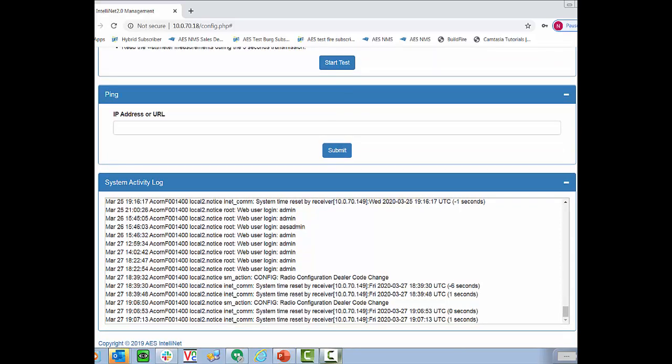Below we have ping where if you're using an IP connection you can ping the multinet receiver. And then we have system activity log. One of the main reasons I'd want you to set up individual usernames and passwords is so you can see exactly who made any changes to the subscriber. Notice here it will always say admin admin admin because this is the only user set up on this subscriber. If you had individual subscriber IDs you could see exactly who did what in your subscriber. This is very handy for service technicians. Two weeks ago the subscriber stopped working and they want to see if there were any changes that caused it to stop working. I would look here first for a cause of the issue.